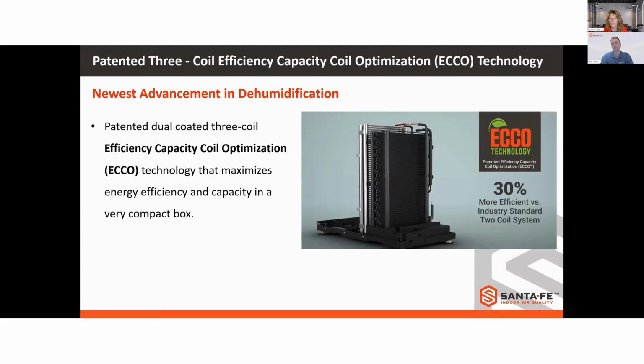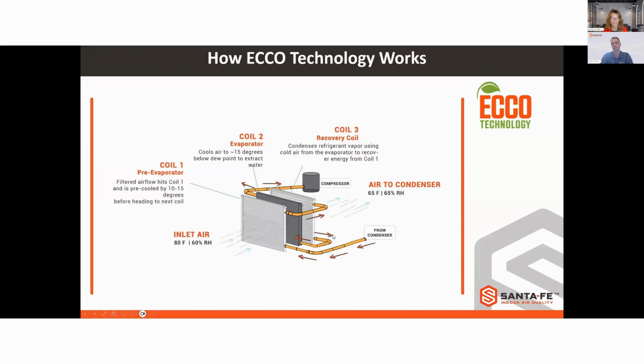And this technology is about 30% more energy efficient versus the standard 2-coil system. And we're going to jump into what this looks like inside the box. So this first coil here is our pre-evaporative coil. What this does is, when the air is coming into it, it's going to pre-cool this incoming air by about 10 to 15 degrees.